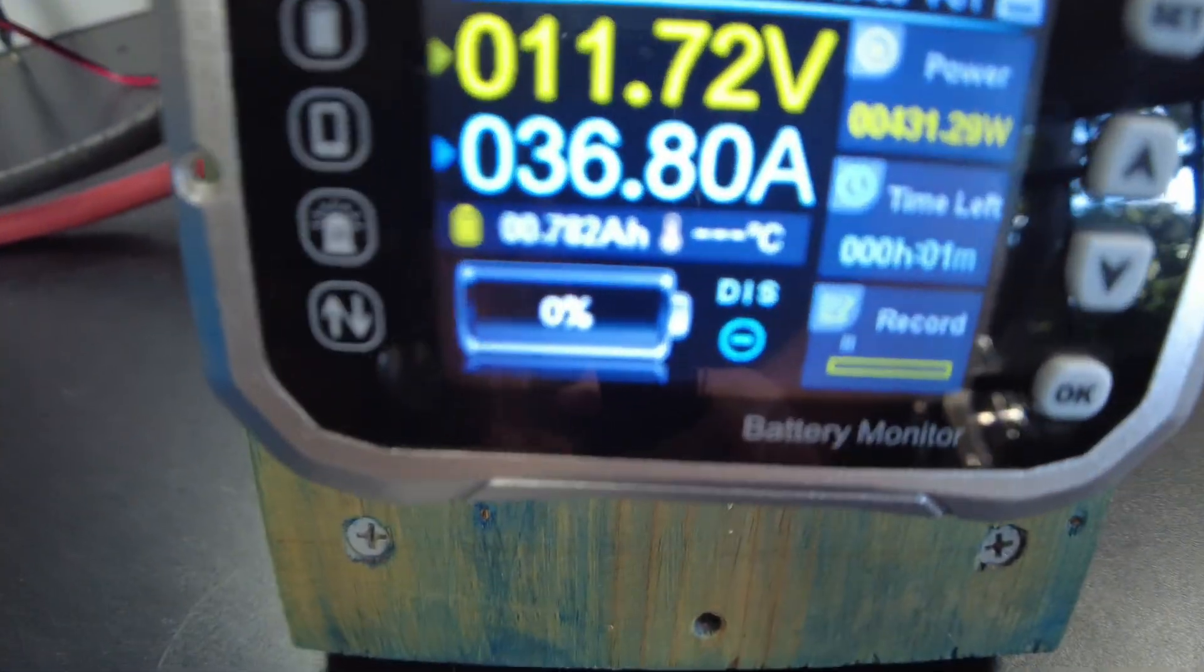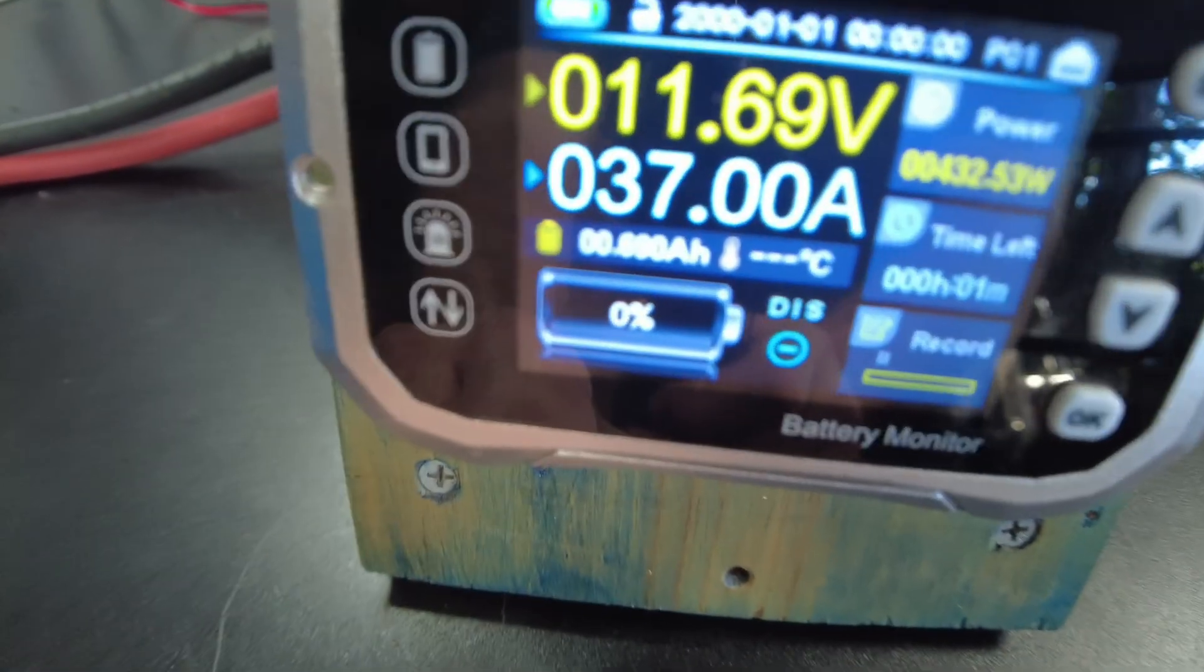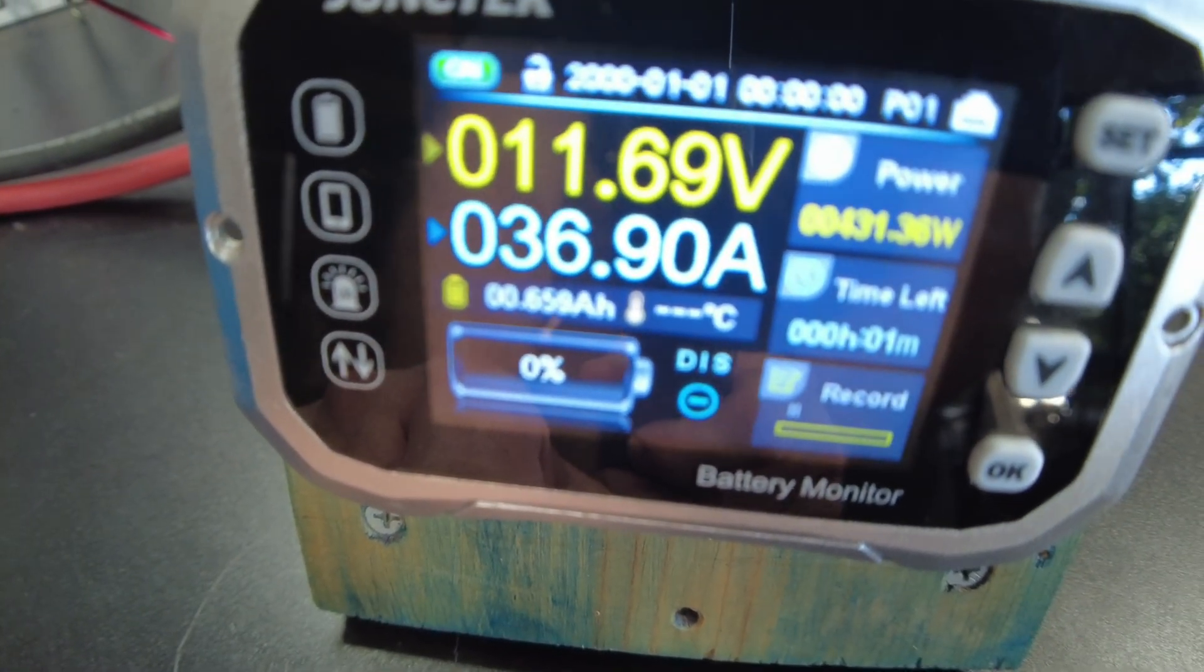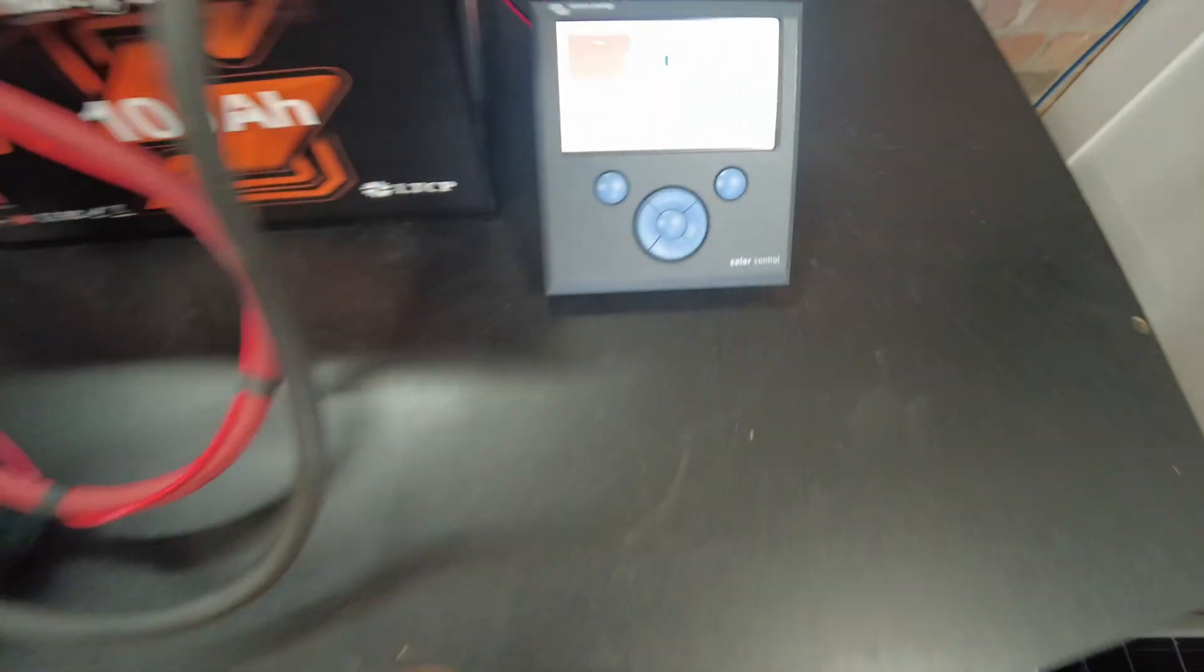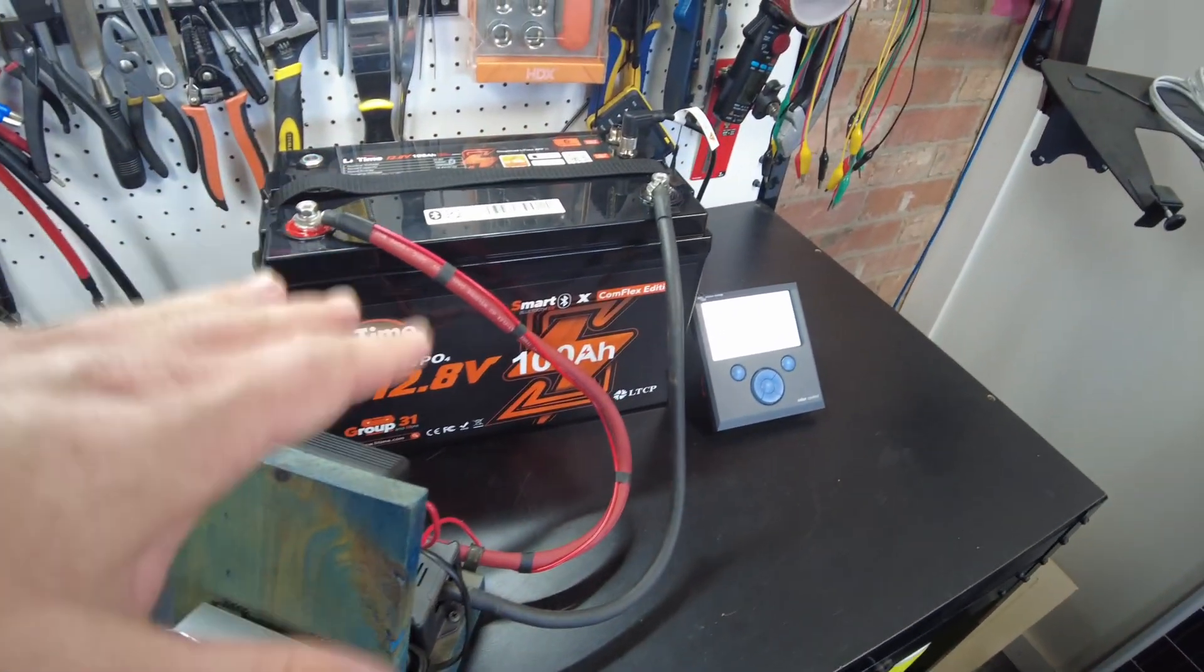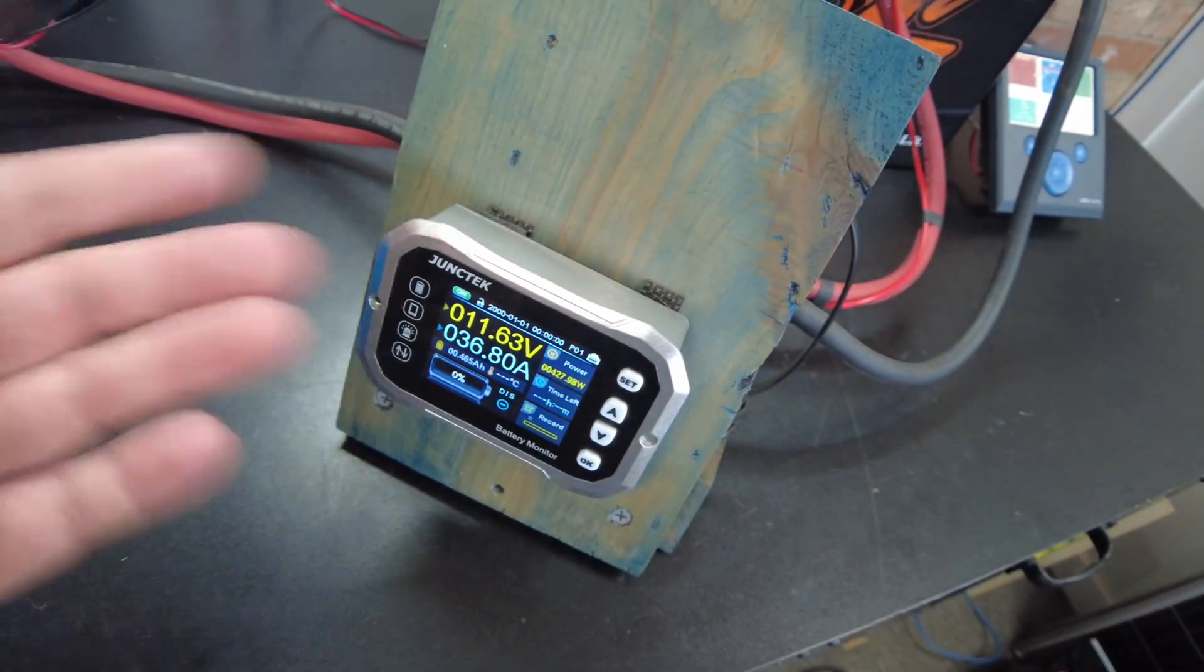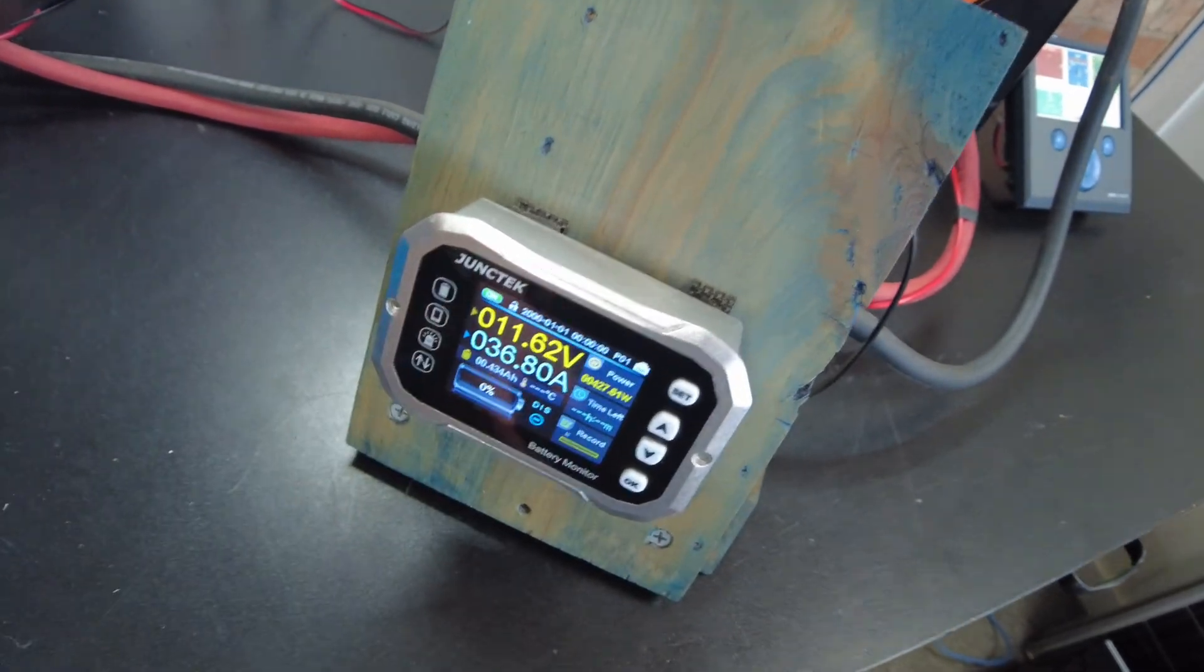All right, so this shunt is saying zero but we still have a little bit left in there. 0.7 amp hours, sorry about that, get it in focus. 0.6 amp hours, still showing 5 percent on the Victron screen. So the battery, I'm guessing, thinks it has more in it than the 100 amp hours that we set on this, because this is only going to count down 100 amp hours.